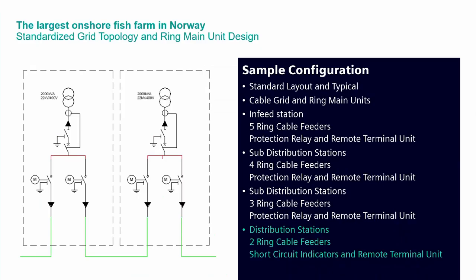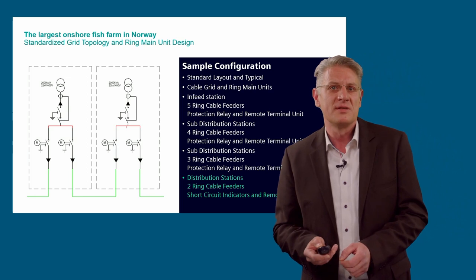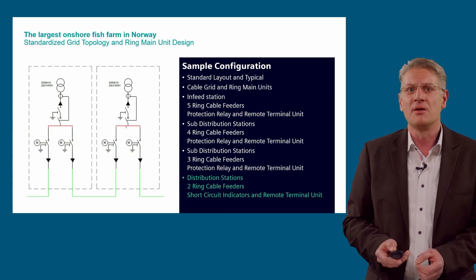Not only does the secondary system have a high level of standardization — an even more standardized design is implemented in the defined ring main units for the plant. The following ring main units are used for the project: an in-feed station with five ring cable feeders with protection relay and remote terminal unit; sub-stations with four and three ring cable feeders with protection relay and remote terminal units; and distribution stations with two ring cable feeders, short circuit indicators, and remote terminal units. The single line shows two similar distribution stations directly connected via cable equipped with load breakers — the most standard design of a medium voltage switchgear in distribution grids.